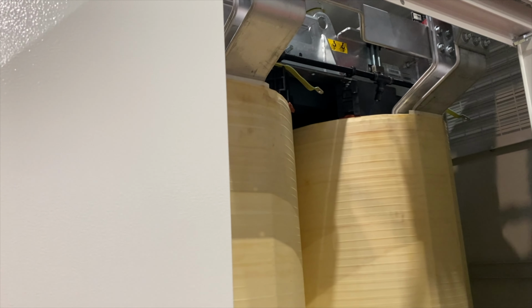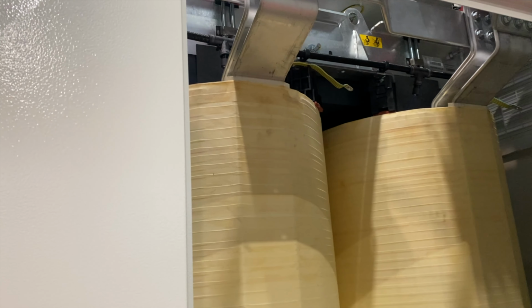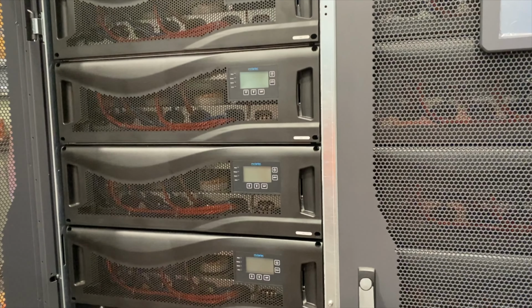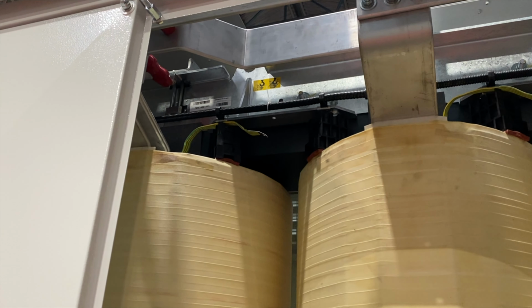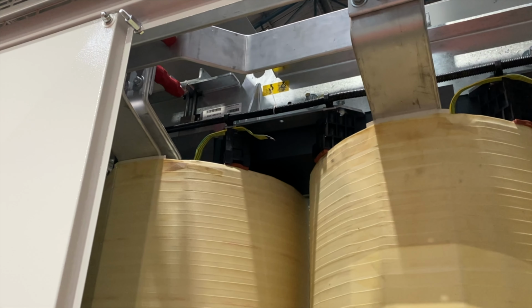Quite unique, 3.5 MVA for a dry type, that's on the big side. For converter transformers, we had concerns about harmonics and concerns about resonant frequencies. So we had to develop a transformer with a gapped core to give more inductance into the system, to counter the frequency converter protection system.